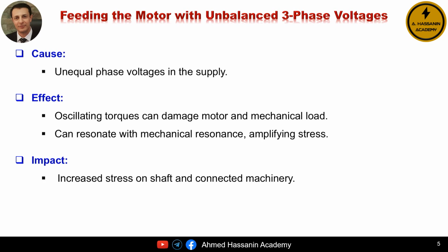The shaft, bearings, and connected equipment all experience extra stress. Over time, this can lead to wear, overheating, or even mechanical failure if we ignore it. So, the key takeaway is unbalanced supply voltages aren't just an electrical issue, they have a real mechanical impact too. That's why monitoring phase balance is so important in motor operation.